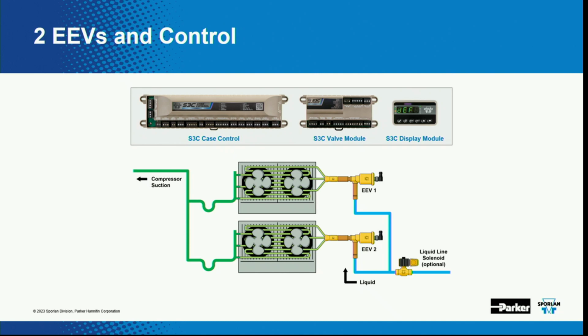We can have two coils if we use an additional valve module. So we have the main case controller, a valve module, and then we always have to have that display module. In this case, the valve module will drive the second stepper motor, and I've got one liquid line solenoid feeding both of those. Question: is two the max you could have for one controller? For one case controller, I can have one metering valve - if I've got a second coil, I'll need another valve module. How many of those can you add up to? Two - I can put two valve modules on. Okay, so a total of three. Yeah, I think three, you'd run out of room.